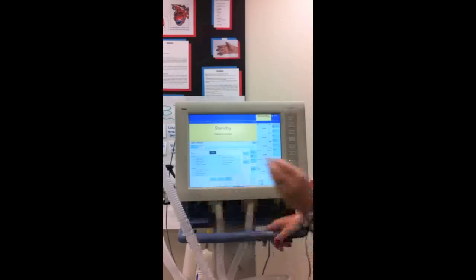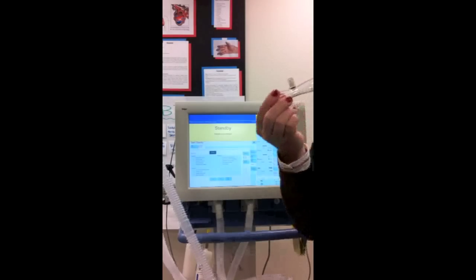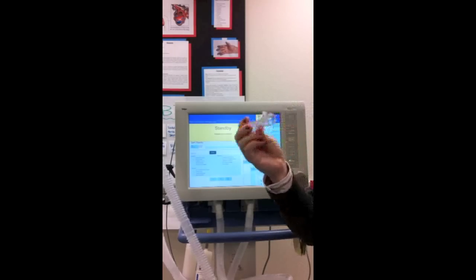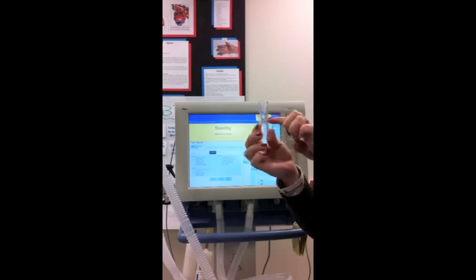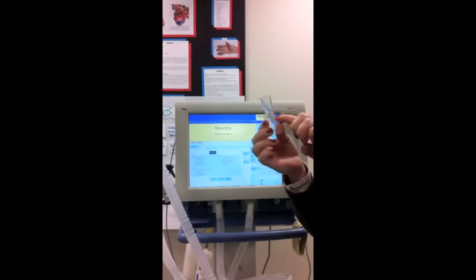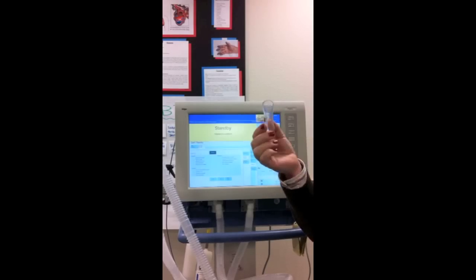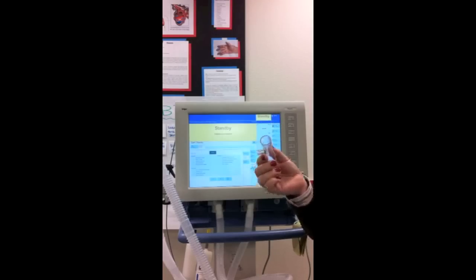Our flow sensor is like the flow sensor on the Galileo, except it looks different. It has little gold spikes in there that are used to check the flow. If this is not working, the ventilator won't work. You'll get check flow sensor errors. So this needs to be working and in good order. If not, you have to replace it.